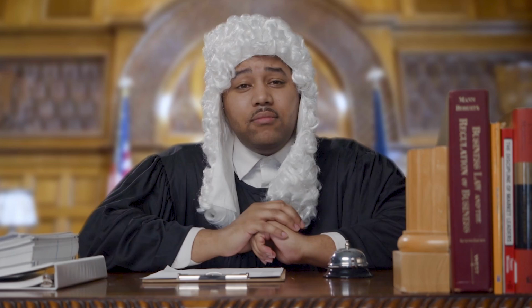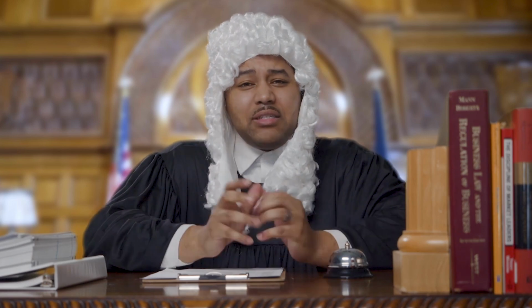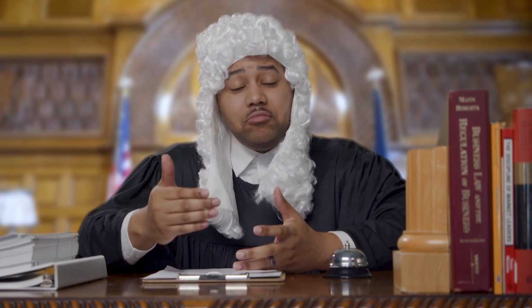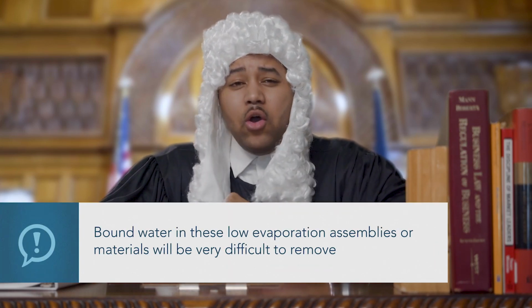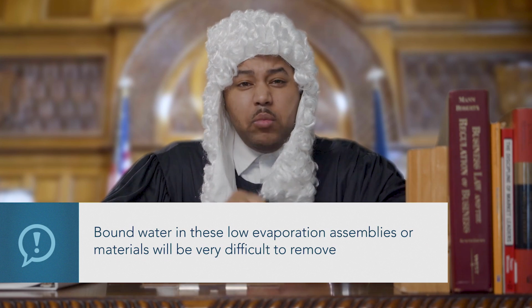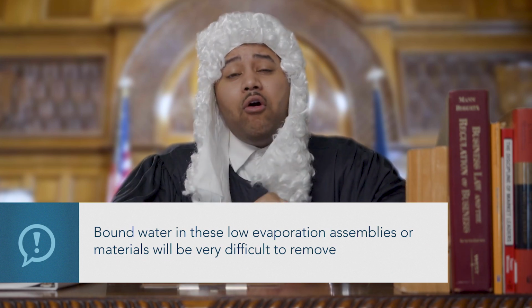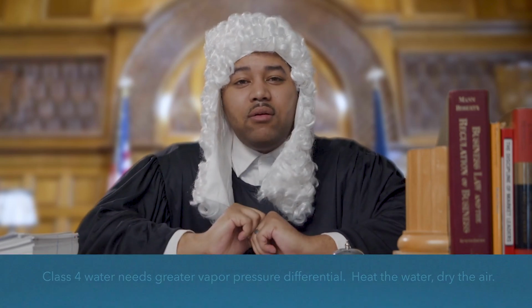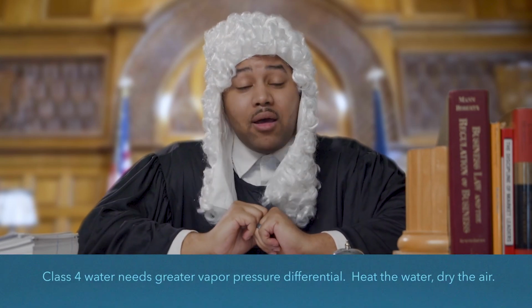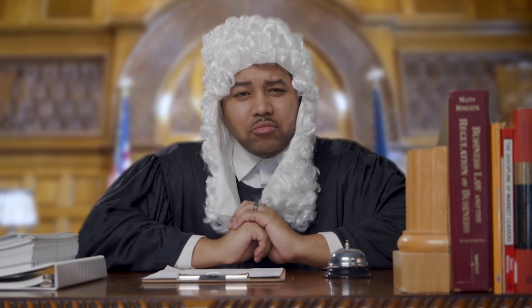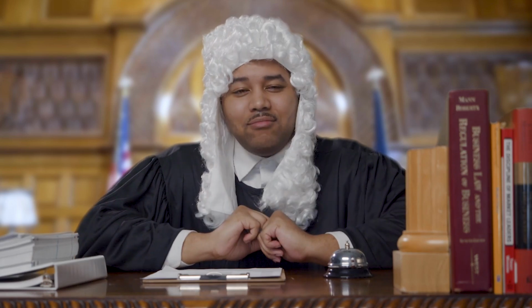Finally, you have Class 4. This one is a bit different, sometimes called specialty drying situations. Now, in this class, the problem is not so much how much evaporation will occur, because the rate of evaporation is low. Rather, it's the fact that the bound water in these low evaporation assemblies or materials will be very difficult to remove. Therefore, drier air is necessary, and that means more dehumidification would be required. It is all quite simplistic in concept. However, a true professional must know the difference in the definitions of class of loss if he is truly going to be accurate. That is all.